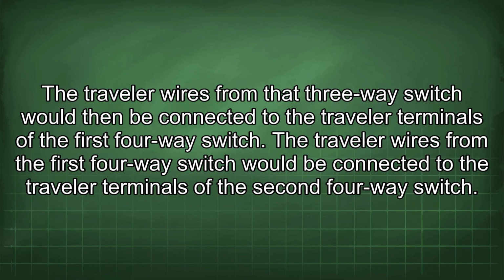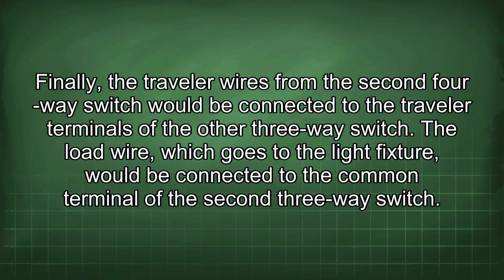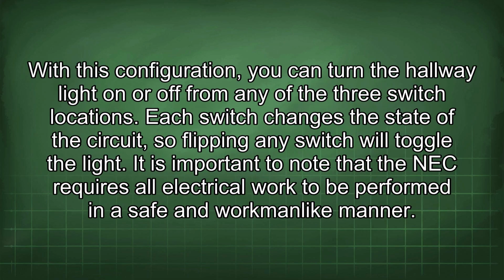The traveler wires from the 3-way switch would then be connected to the traveler terminals of the first 4-way switch. Traveler wires from the first 4-way switch would be connected to the traveler terminals of the second 4-way switch. Finally, the traveler wires from the second 4-way switch would be connected to the traveler terminals of the other 3-way switch. The load wire, which goes to the light fixture, would be connected to the common terminal of the second 3-way switch. With this configuration, you can turn the hallway light on or off from any of the 3 switch locations. Each switch changes the state of the circuit, so flipping any switch will toggle the light.